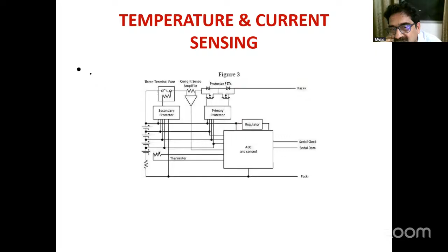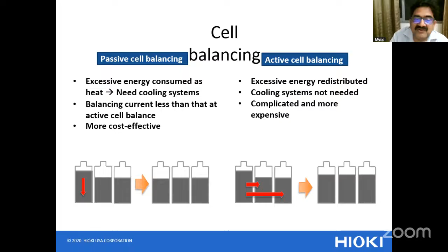So you have passive balancing and active balancing. In passive balancing, we use some resistor to dissipate the excess energy, but in active balancing, from a cell with higher voltage to a cell with lower voltage, we use a DC to DC converter. This is a flyback type of DC to DC converter, where I have a cell with higher voltage and another cell with lower voltage. Then I will activate this DC to DC converter, transfer the energy from the cell with the higher energy to the cell with lower energy, which we call active cell balancing. This is where you find your DC to DC converter applicable.